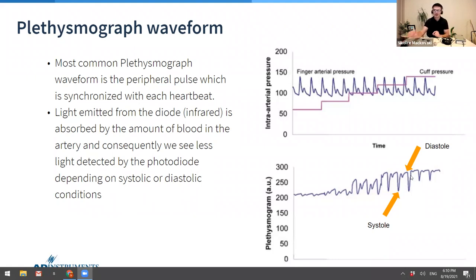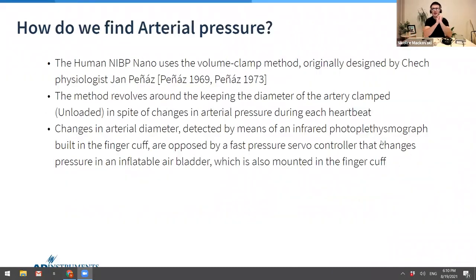Because of this design, a physiologist by the name of Jan Penaz came up with a method called the volume clamp method. As I mentioned earlier, it revolves around keeping the diameter of the artery clamped, or unloaded, in spite of changes in arterial pressure during each heartbeat. Changes in arterial diameter, detected by the infrared photoplethysmograph built into the finger cuff, are opposed by a fast pressure servo controller that changes the pressure in the inflatable air bladder, which is also mounted on the finger cuff.